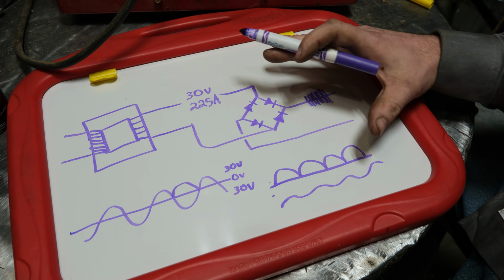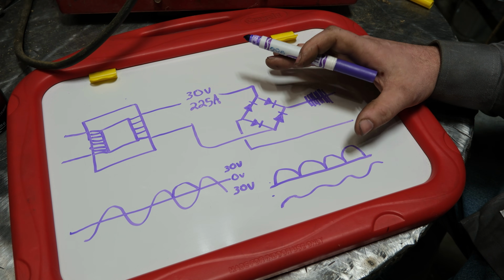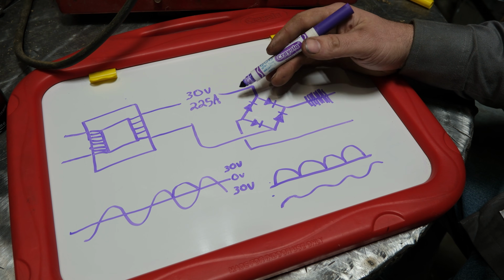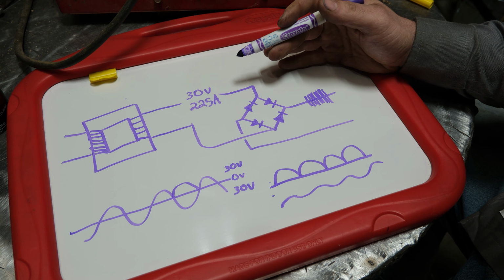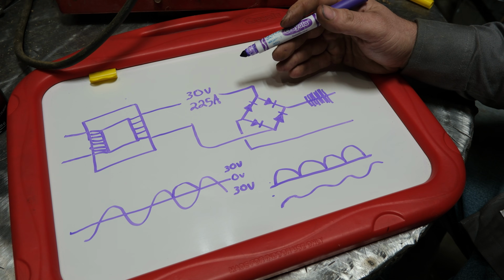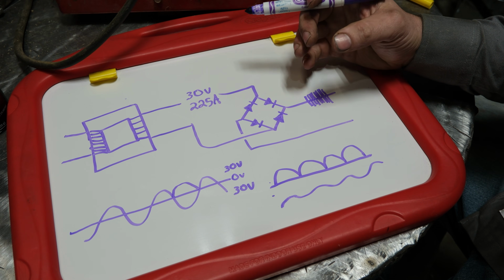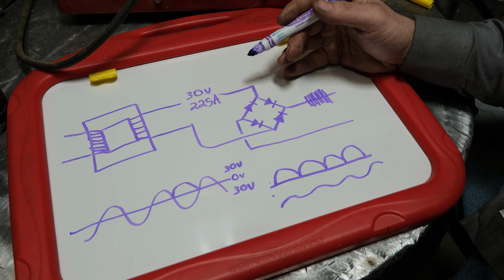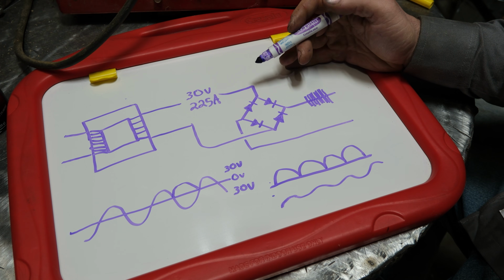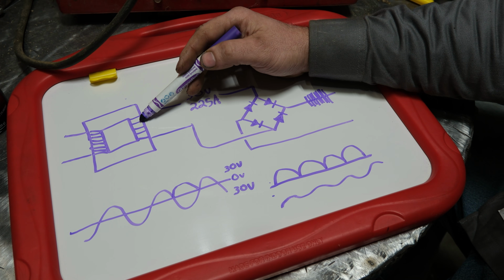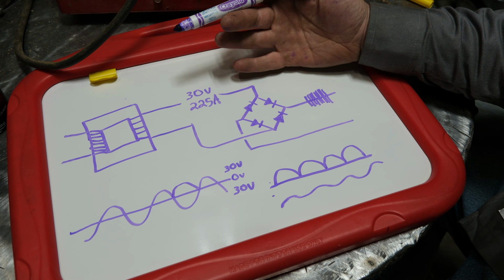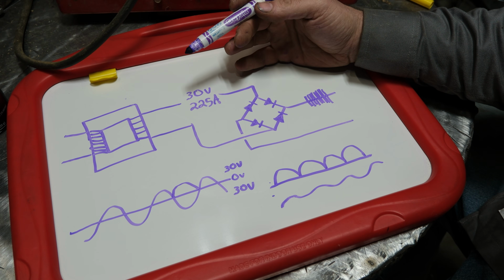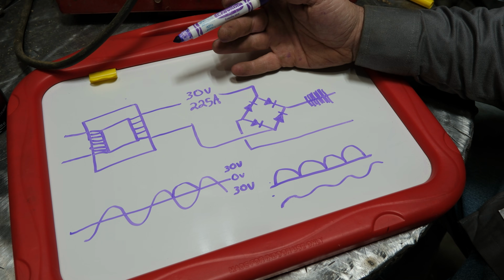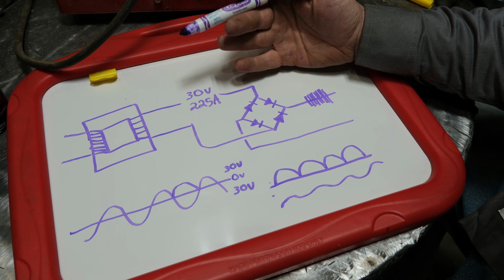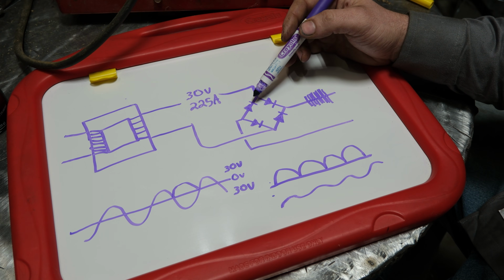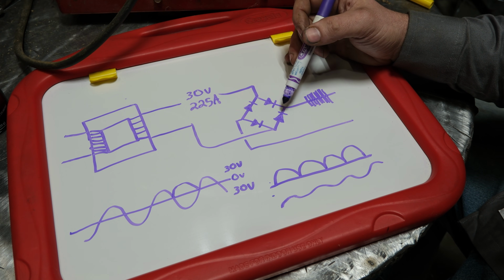The biggest thing you need to understand is that this machine, and basically all older transformer machines, operate on very simple, well understood electrical principles. Because of that simplicity, they tend to be very reliable. If the wire gets nicked and shorts to the core, that would be a problem, but the coating on the wires typically lasts 70 or 80 years in a decent environment without major issues. The main component that would fail is the diodes of the bridge rectifier.